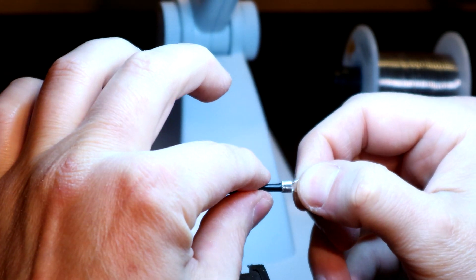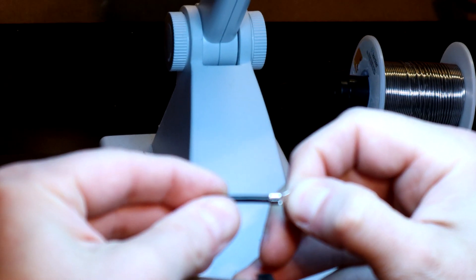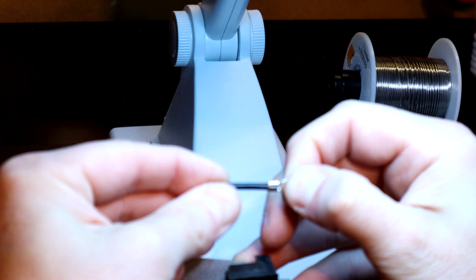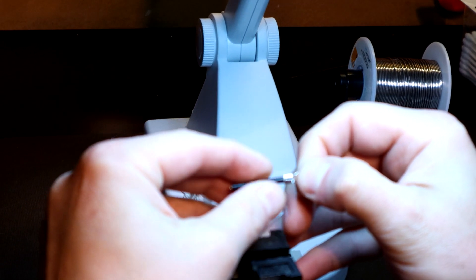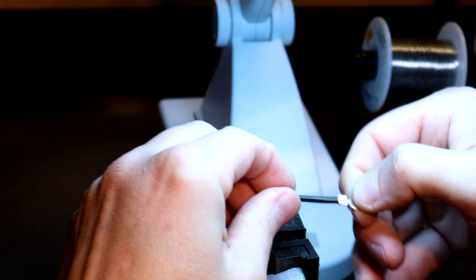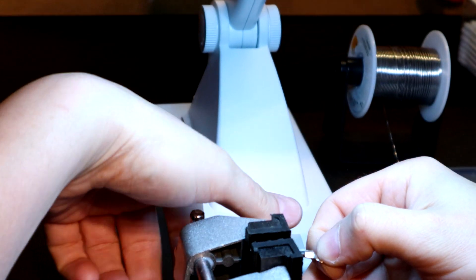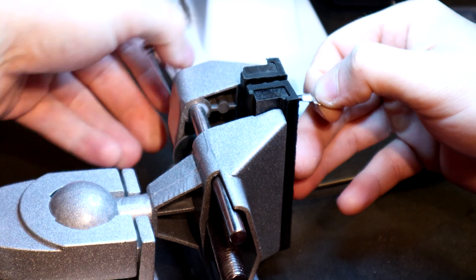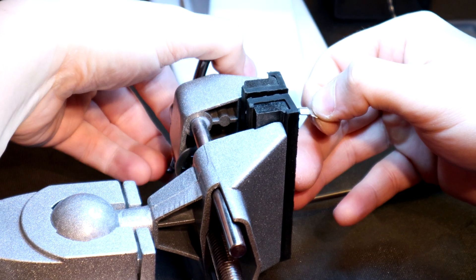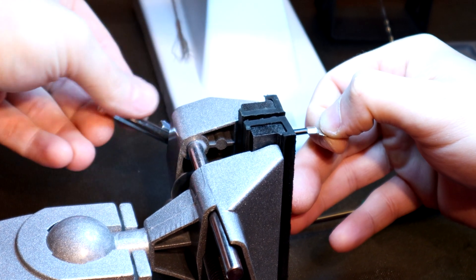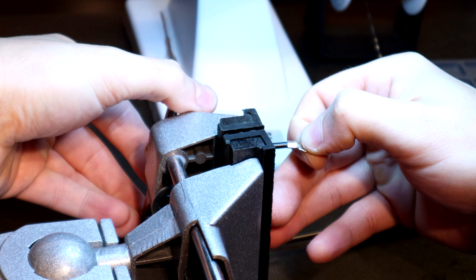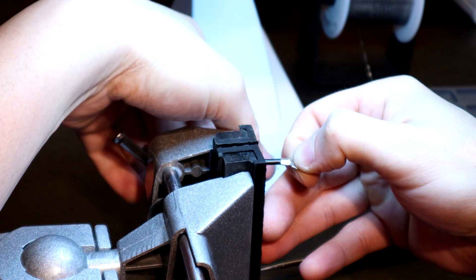Now, mind you, if this is connected to a VFD and there's slight tension on that cable, over time, you could get that separation and that could be catastrophic. So, a real easy fix. I'm going to lock her into the device right here. We'll do this carefully. I'm just going to come out and show you how fast this is to fix. Just lock it in.